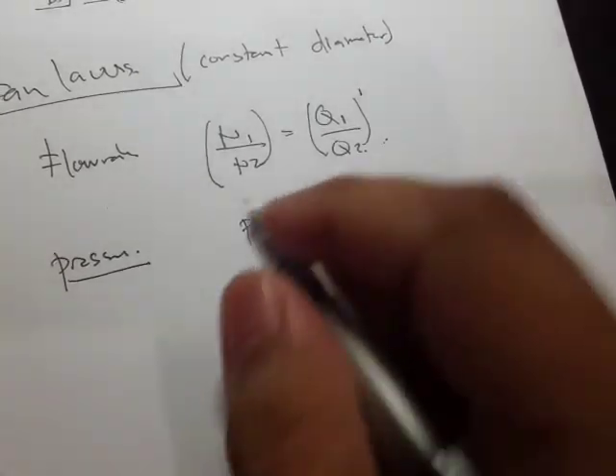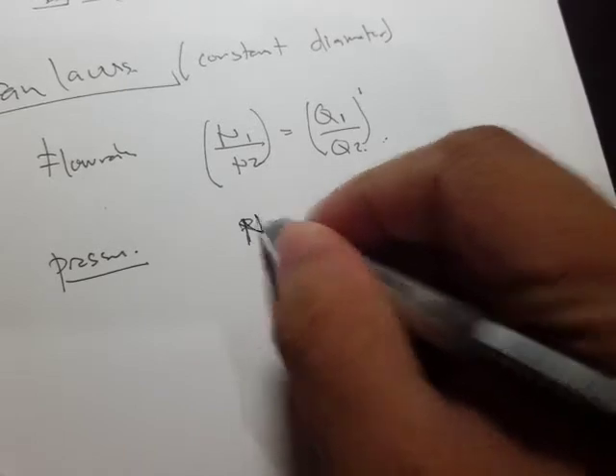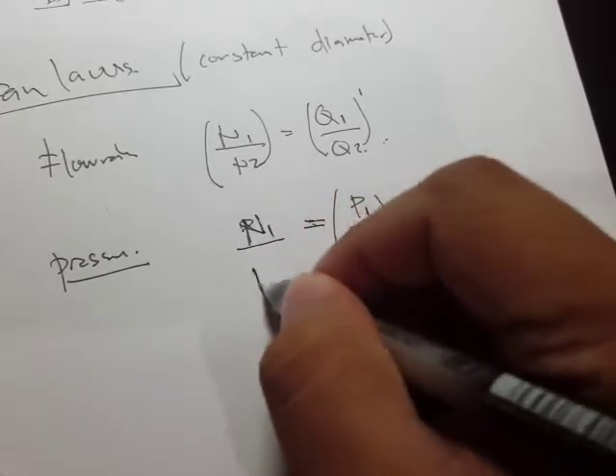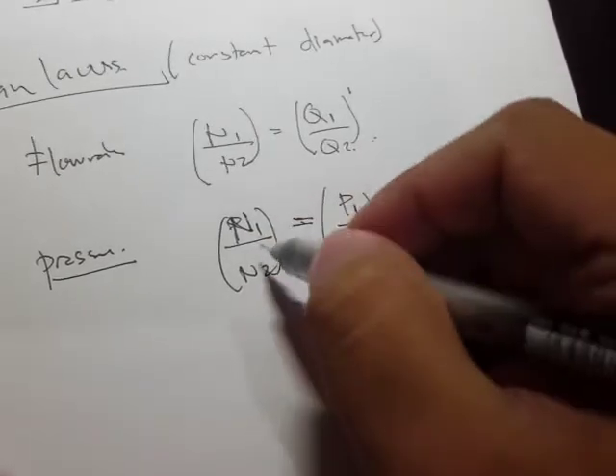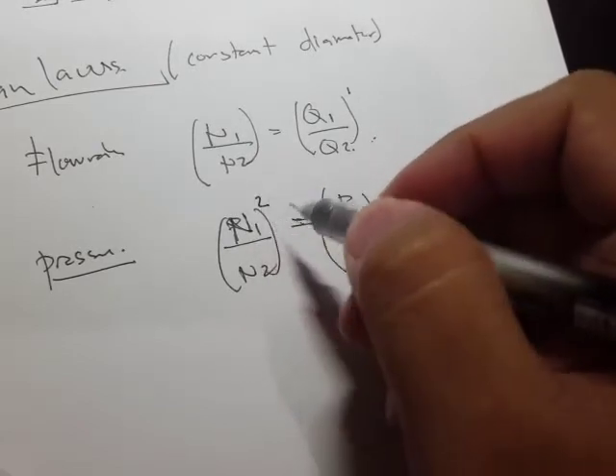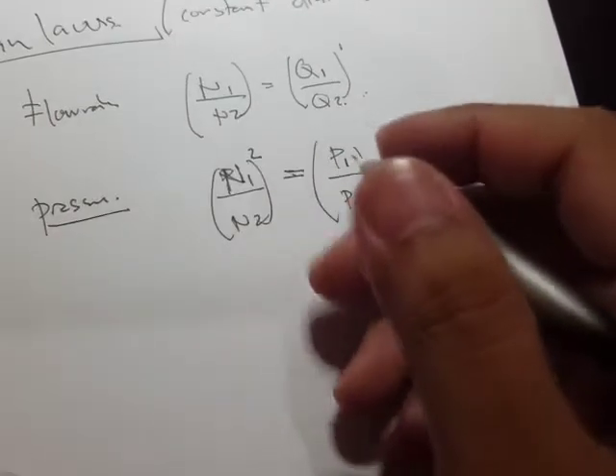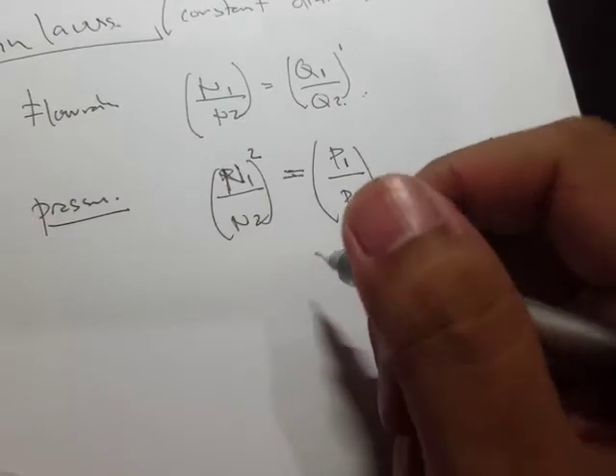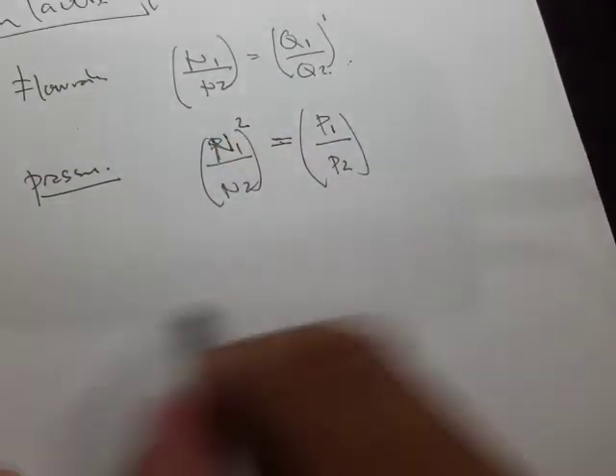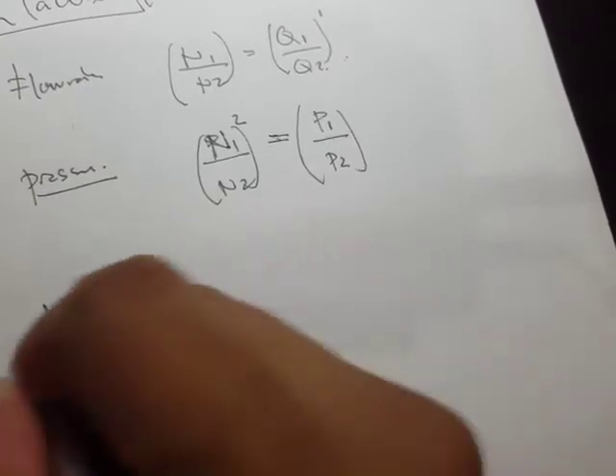For pressure — let's say P₁ over P₂ — the effect is n₁ over n₂, but this time the speed ratio is squared. So the relationship between speed and pressure follows a square law.